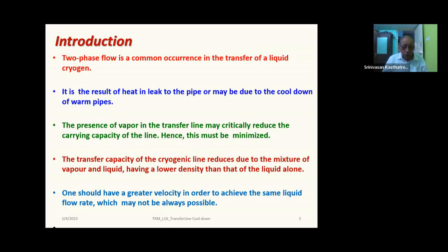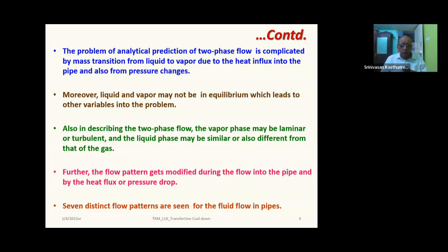Now also, in case you have a large quantity of vapor, then you have to apply larger pressure for transfer, which will lead to increased velocity. Okay, but sometimes this may not always be possible because the line may not be rated for such high pressures. That is one thing. Secondly, the joints, whatever you are making, may not be adequate, so they can give up at some places. Right. Okay.